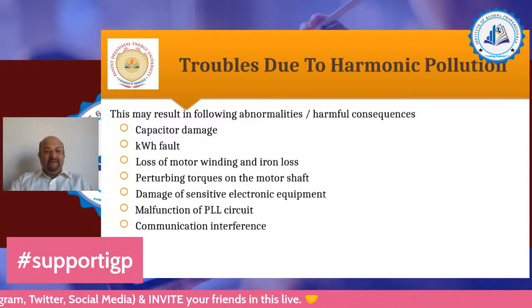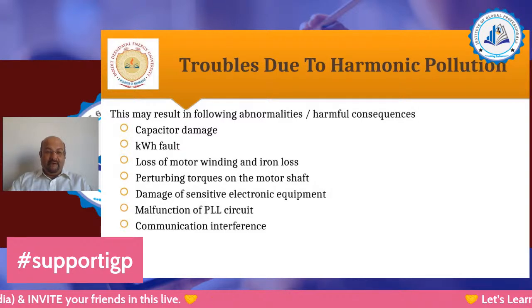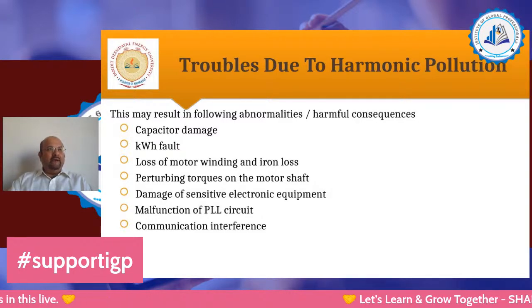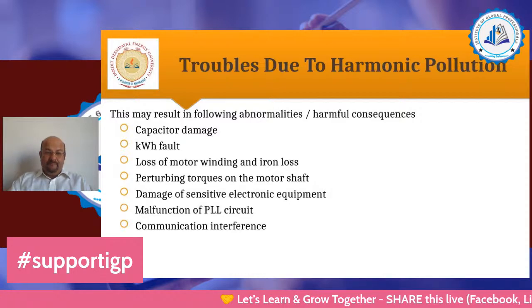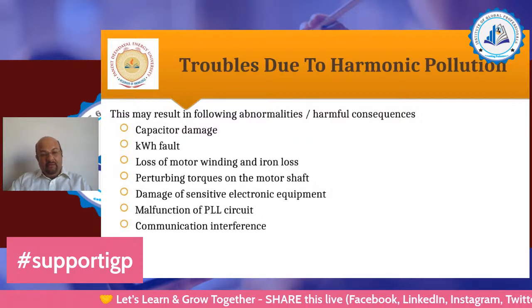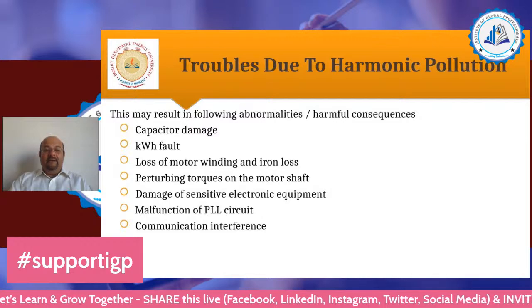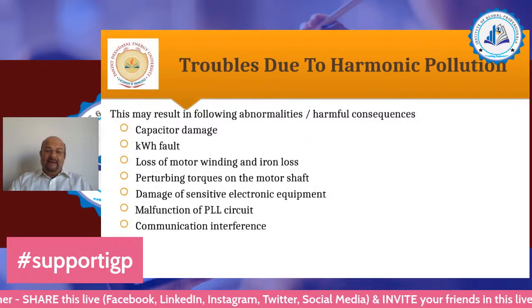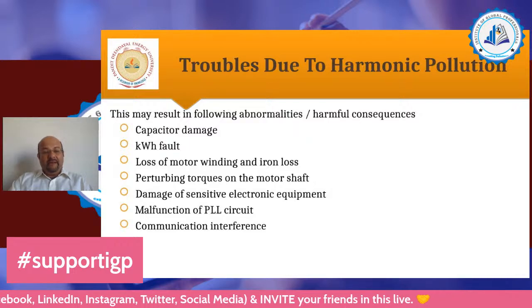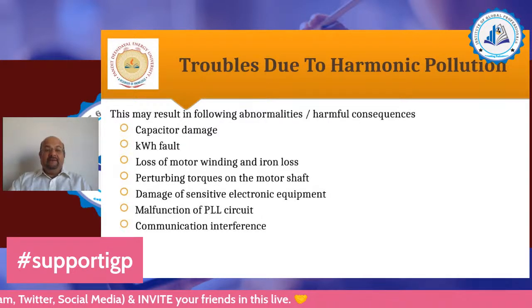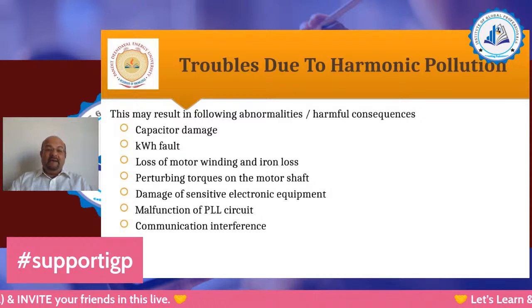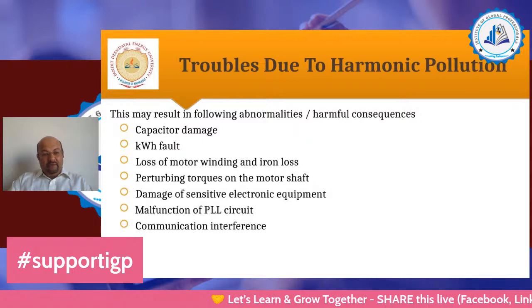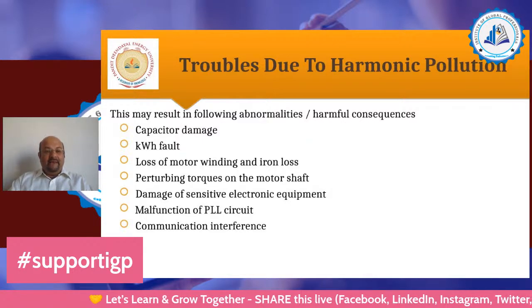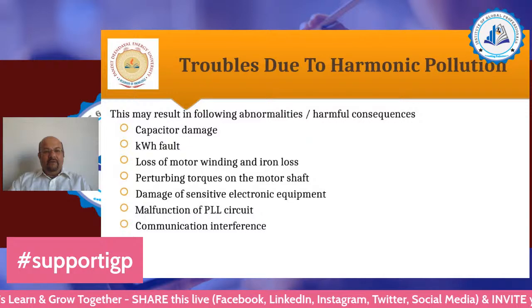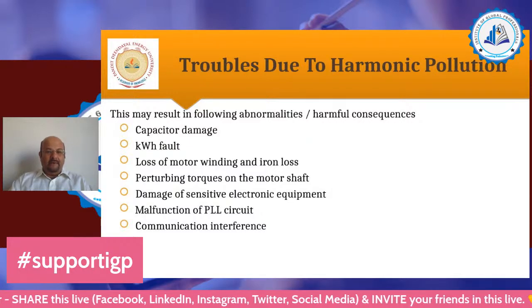Again, kilowatt hour is a unit of electrical energy measurement. And we know that due to distortion of the sine wave, maybe in voltage or in current or in both, when this energy is being measured with electronic equipment or digitally, in short, the zero crossing is not decided, and there are multiple zero crossings. Due to that, there may be a calculation fault. So it is known as a kWh fault. kWh is the unit of energy, 1 kilowatt hour.